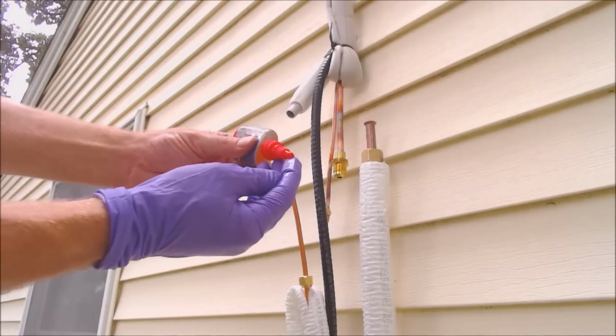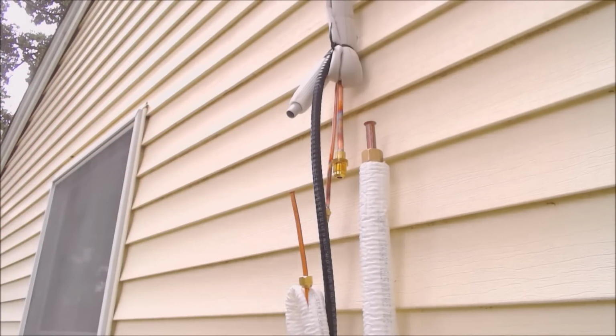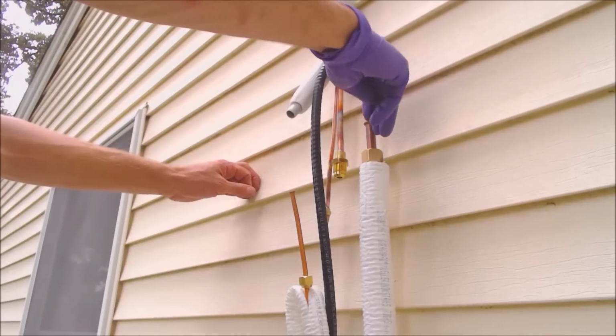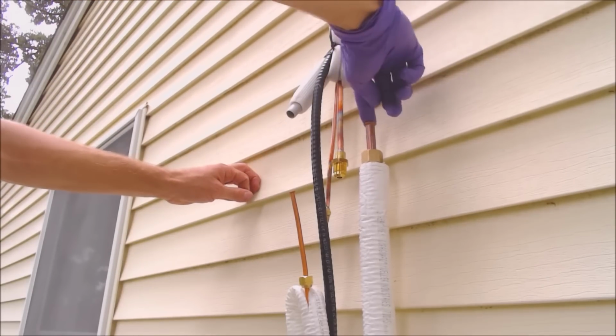And another thing I see a lot of people doing is putting lubricant on the threads of the flare face. That messes up the torque value. A lot of them are dry flare face, but once again, you read the manufacturer's literature in reference to doing that. Also, a lot of people, including myself, have put a gasketing material such as refrigerant oil or Nylog on the flare face before you tighten it in.